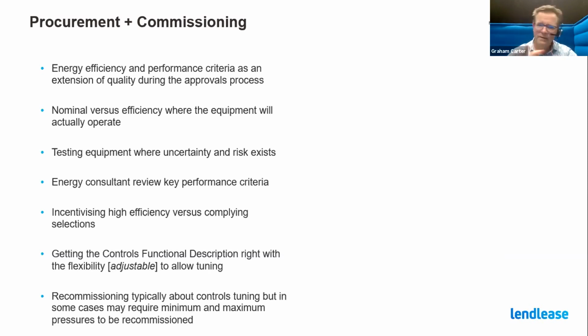If you get this all right, we haven't found that we've had to recommission buildings wholesale. It typically comes down to controls tuning, but in some cases you do have to come back and reconfirm minimum and maximum pressures for minimum and maximum volume. That's typically where there's been a series of fit-outs disruptive to the base building commissioning.